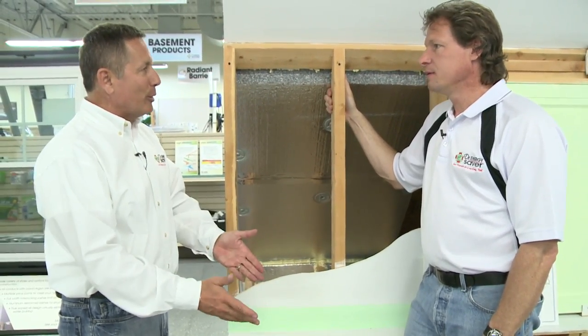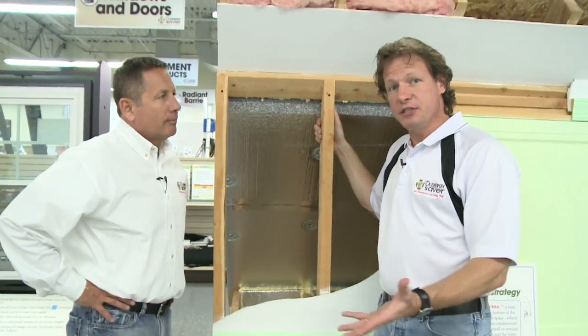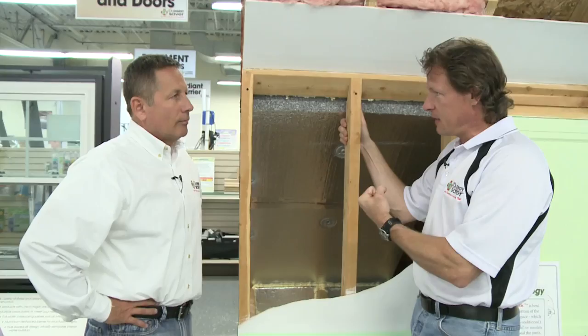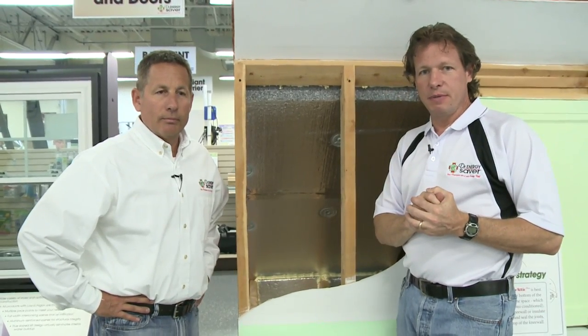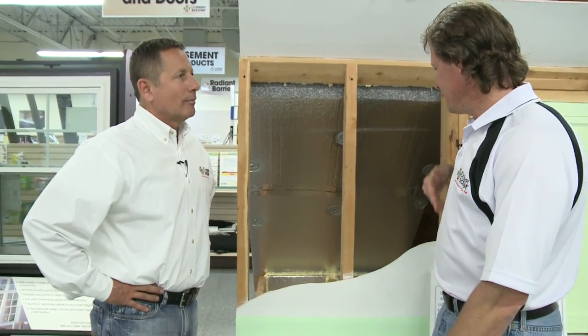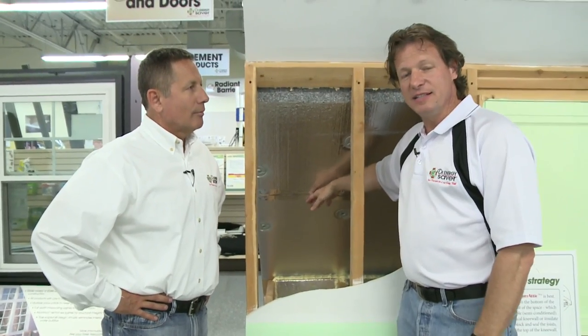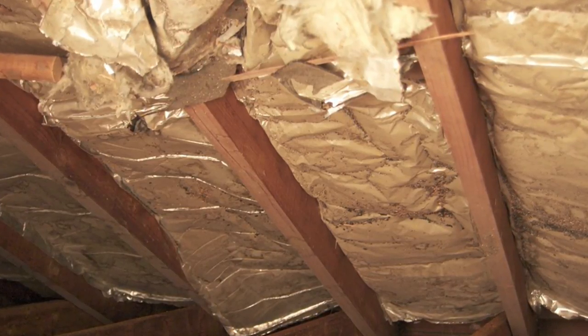By the time the air is coming out into the room, it's a lot cooler than it would be if it weren't being affected by that cold air. One of the effects of having too much air leakage in your house in the wintertime is having too dry of a house. Because when outdoor air leaks in to replace air that escaped, we're heating that air — and for every one degree we heat the air, we reduce the relative humidity by 2.2% unless we add water. We had one client whose house was very dry, so they put a humidifier on their furnace duct system, added humidity to the house. But they had a knee wall space, and the air from inside the house was leaking into the knee wall space and condensing on the cold surfaces, causing condensation — actually wet, soaking insulation and wet wood back there — which will cause a big mold problem.